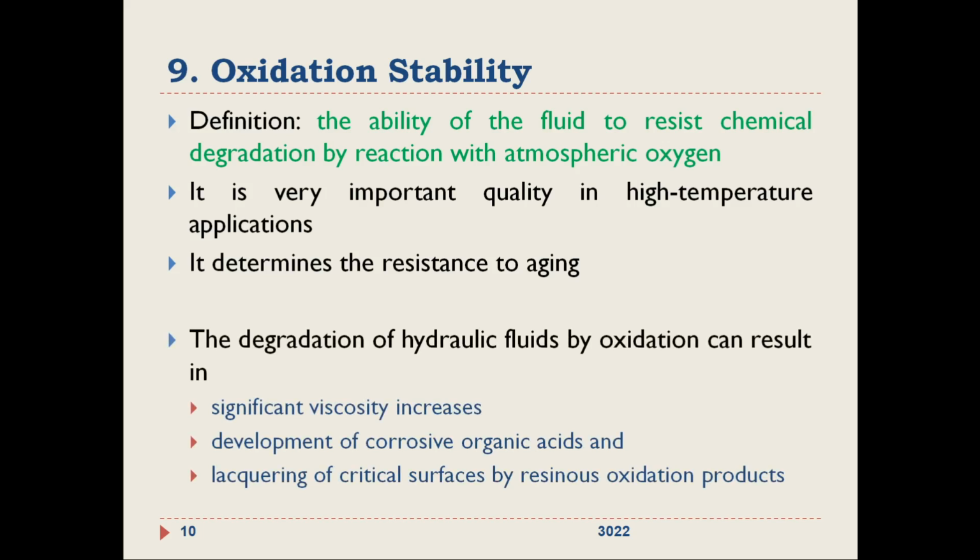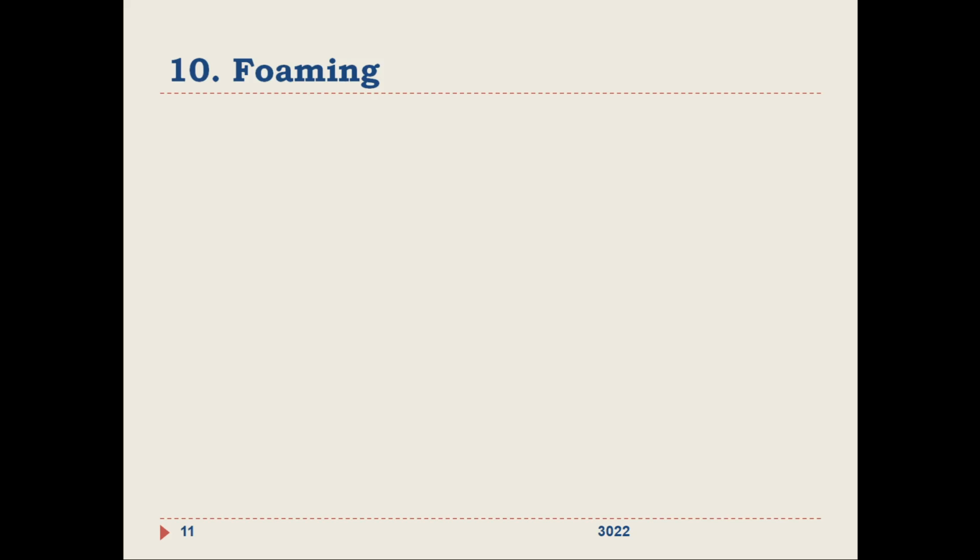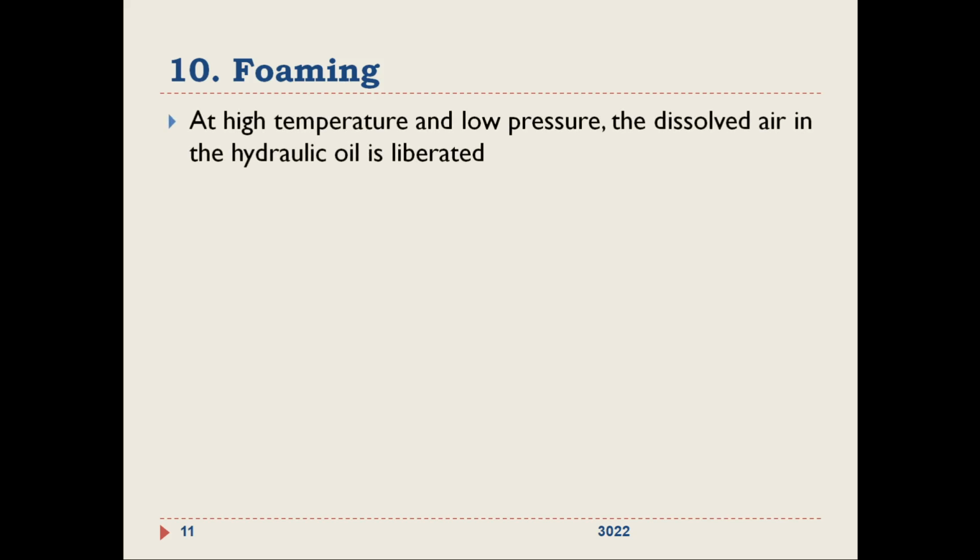If the oil is oxidized by reacting with atmospheric oxygen, what will happen? There will be a significant rise in viscosity, development of corrosive organic acids, and lacquering of critical surfaces by resinous oxidation products. These are the effects of oxidation. The 10th property is formation of foam.